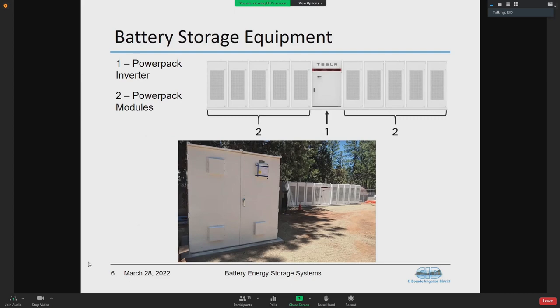This is generally what the BESS facilities are composed of. They're pretty simple, with three big components. The first is the Powerpack Inverter, which converts AC power to DC storage in the batteries. Depending on the site, you have several battery pack modules, which can be added or subtracted depending on the load. The last is that big box on the bottom, usually a switch gear, which intercepts the incoming PG&E power to the site and ties it to these new systems. That allows it to direct power from PG&E, from the battery, or a combination of the two, to meet loads at the facility.